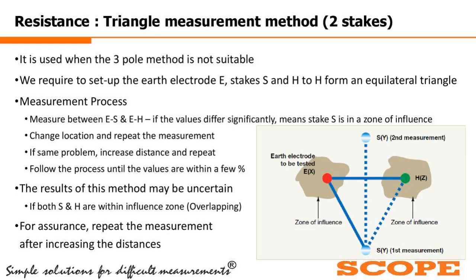substantially, then we have to change the location of S, create an equilateral triangle once again, and repeat the measurement. This is because of the zone of influence, as shown in the picture, overlapping with S. In the picture, the zone of influence is limited to the case where we have the red and green dots, but in the case of the blue dot, it is not in the overlapping zone. So we are expected to see the difference in value in the first measurement itself. If the difference is not there, then we need to repeat the measurement by moving to a second position.